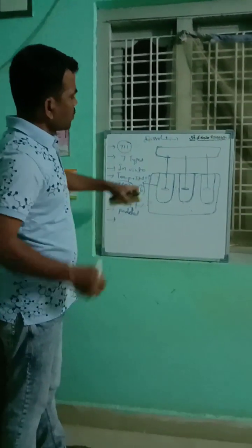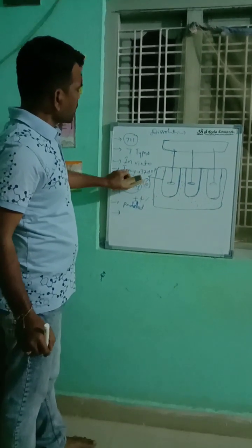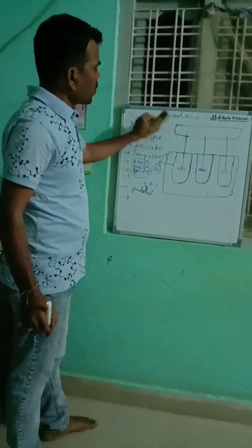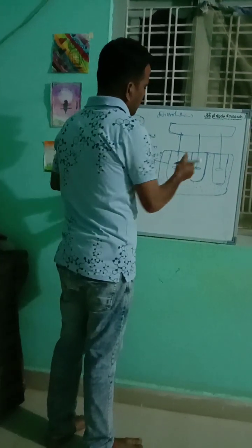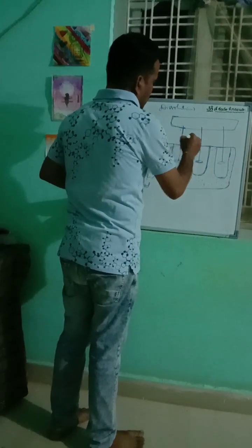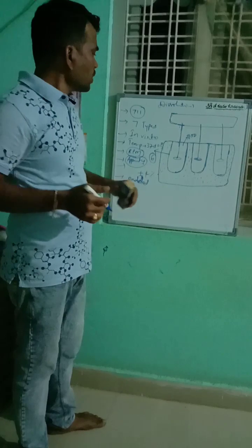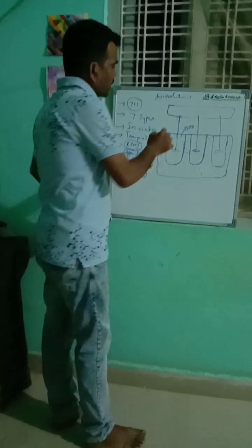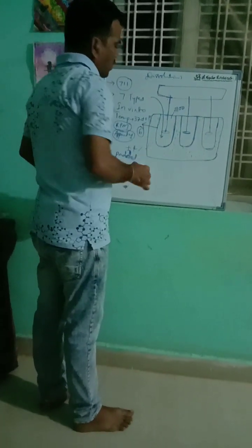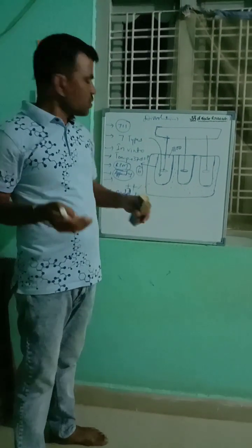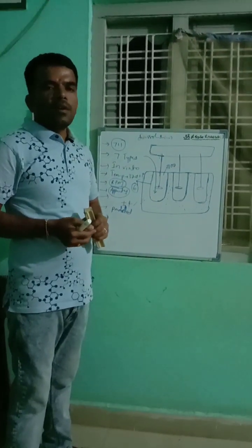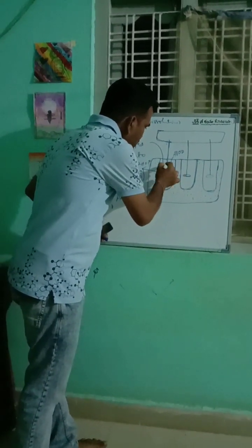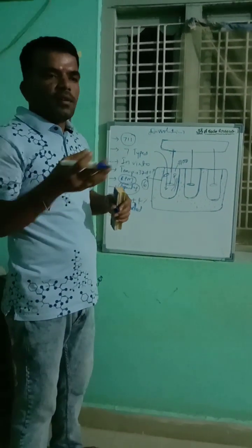Here we pour the water and maintain the temperature of 37 degrees during the analysis. After reaching the temperature, we pour the buffer into each vessel, 900 ml. Either it is phosphate buffer or 0.1 normal HCl. You pour the buffer into each of the 6 vessels, and after that you add the tablet in a vessel. If it is a normal tablet, you can use the paddle apparatus. If it is a floating tablet, when you add it, it can move here and there. There is no fixed place. It is a very delicate tablet.